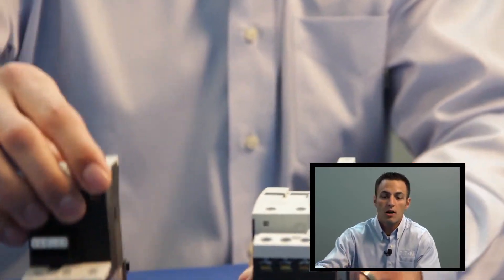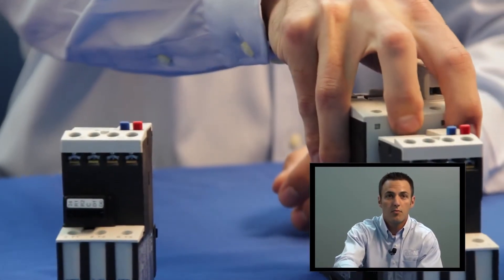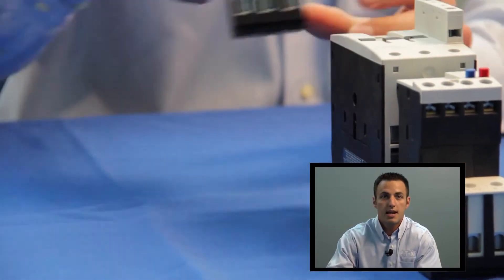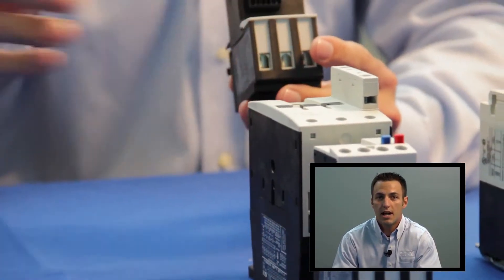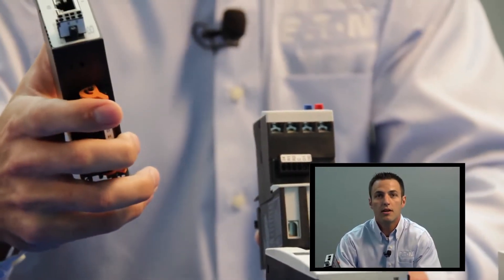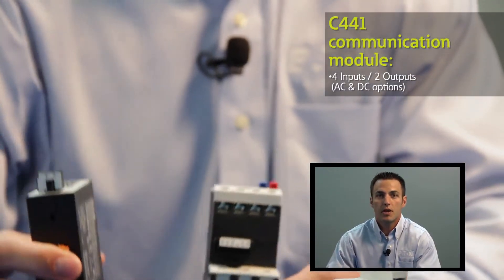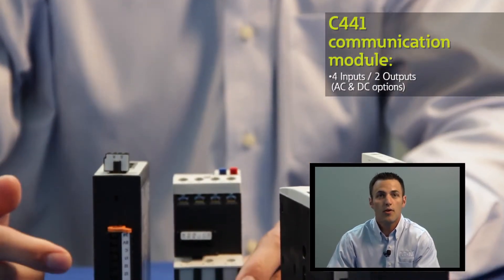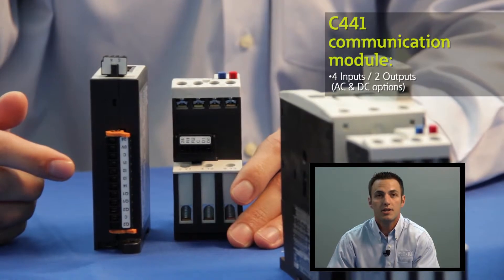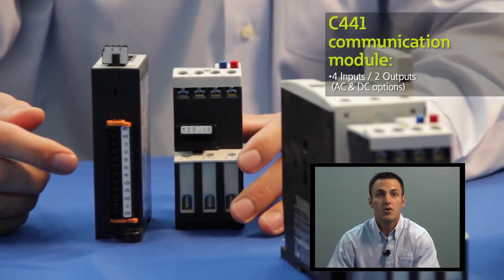For customers who also wish to not only monitor but also control the starter over communications, that same C440 XCOM can be connected to a DIN rail mounted C441 communication module. This provides the user with four inputs and two outputs in both AC and DC configurations giving them the ability to control the starter unit.